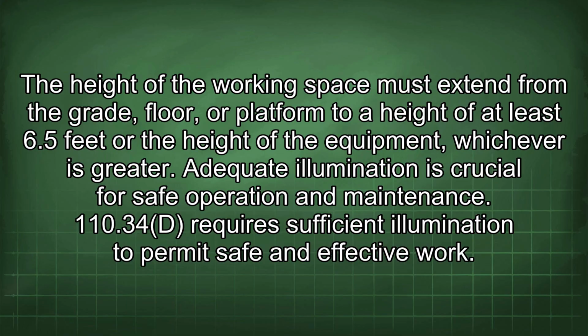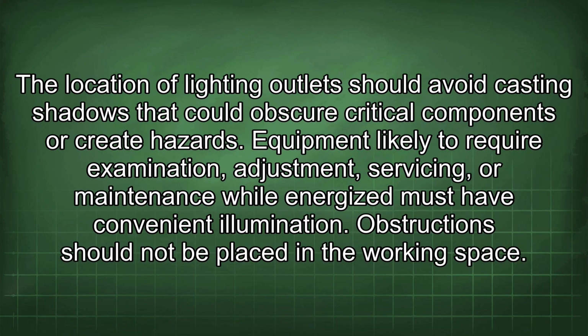110.34(D) requires sufficient illumination to permit safe and effective work. The location of lighting outlets should avoid casting shadows that could obscure critical components or create hazards. Equipment likely to require examination, adjustment, servicing, or maintenance while energized must have convenient illumination. Obstructions should not be placed in the working space.